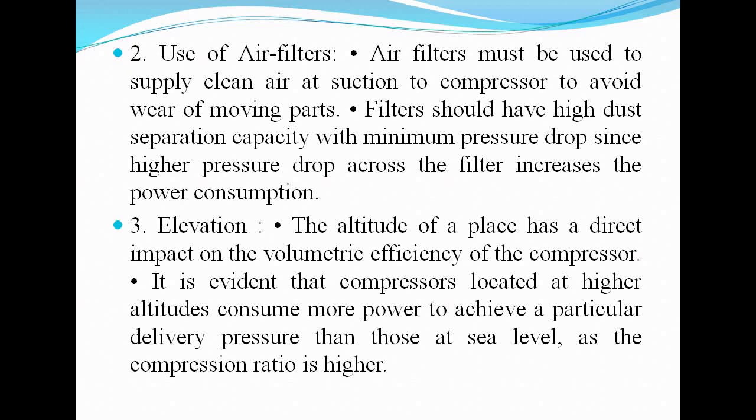Then, use of air filters. As I told you, air filters must be used to supply clean air at suction to the compressor to avoid wear of moving parts. The filter should have high dust separation capacity with minimum pressure drop, since a higher pressure drop across the filters increases the power consumption. So that's why the filter should be clean and there should be minimum pressure drop, so that there would be minimum power consumption.